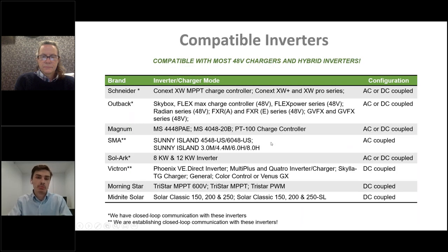Here's a list of our compatible inverters that we're working with, and we always recommend here at Fortress that you size your battery for double the size of the inverter you're using. So for simplicity's sake, let's say we're using the Sol-Ark 12kW - we'd recommend around a 24 kilowatt hour battery, although you could use one Sol-Ark with the eVault 18.5 as a turnkey package. The general rule of thumb is you want it to be double. So for example, Schneider has a 6.8 48 inverter - you'd want the battery to be around 13 kilowatt hours.